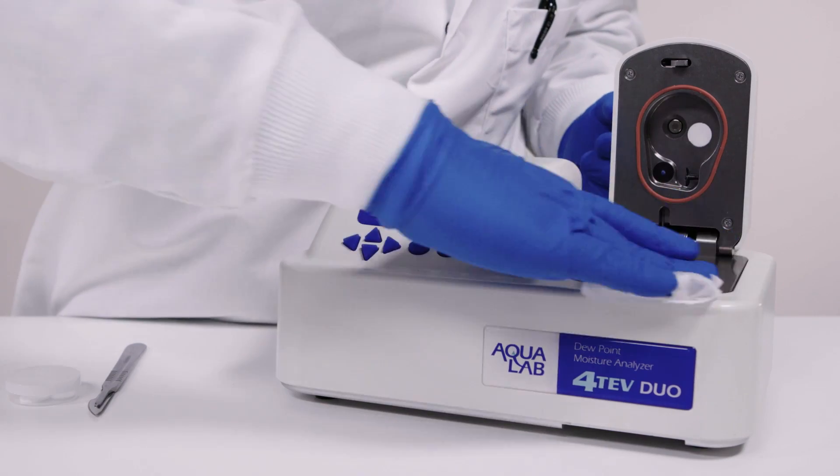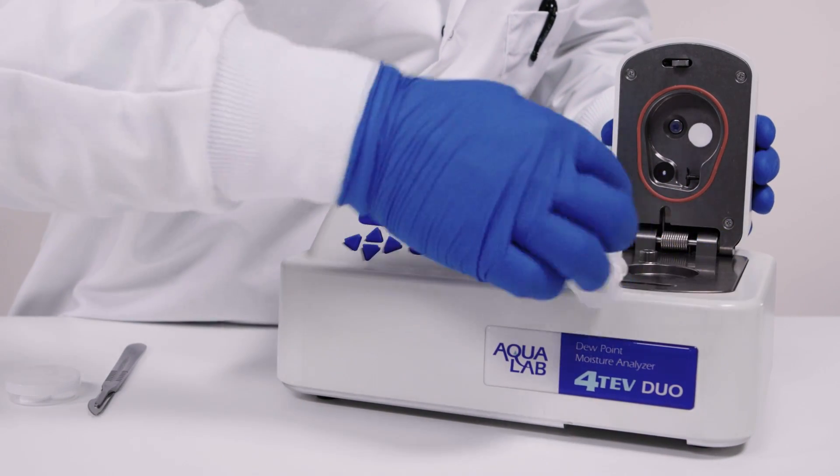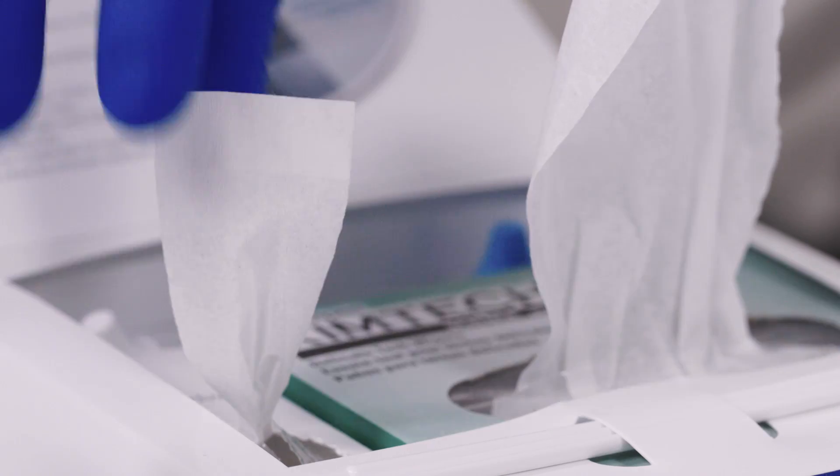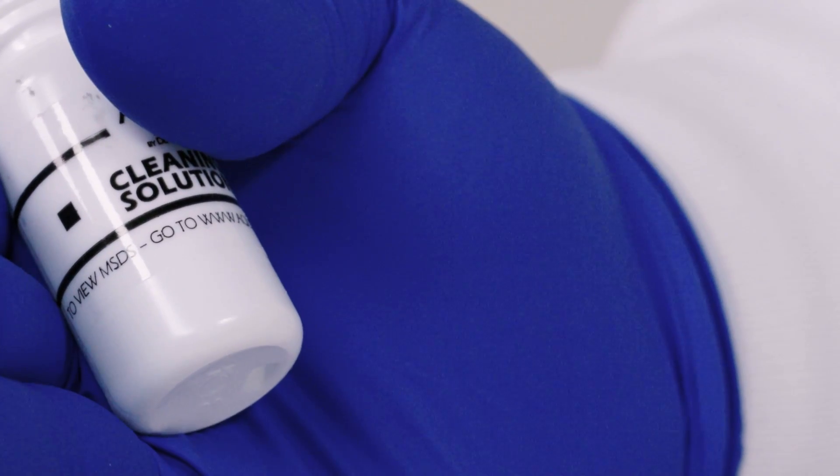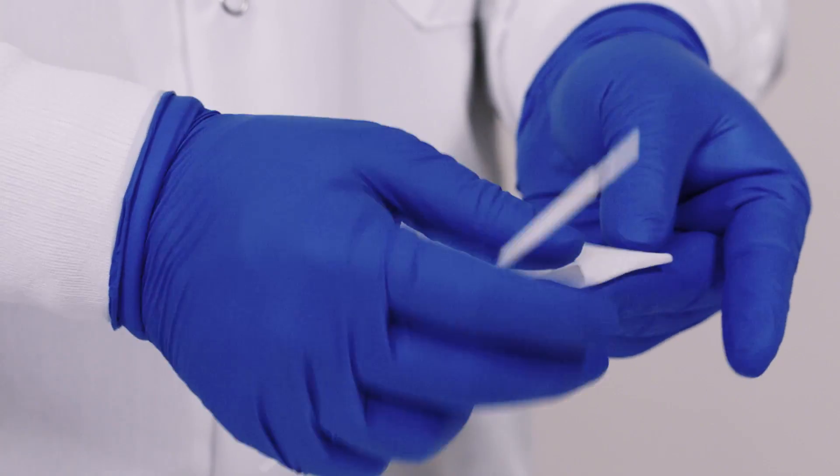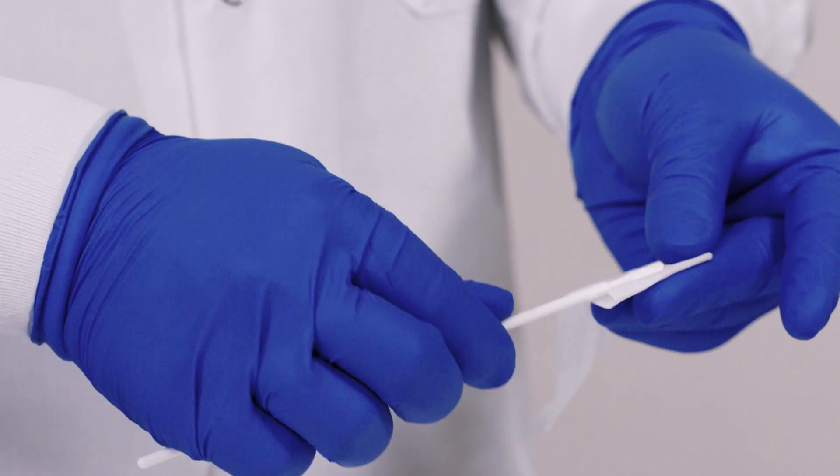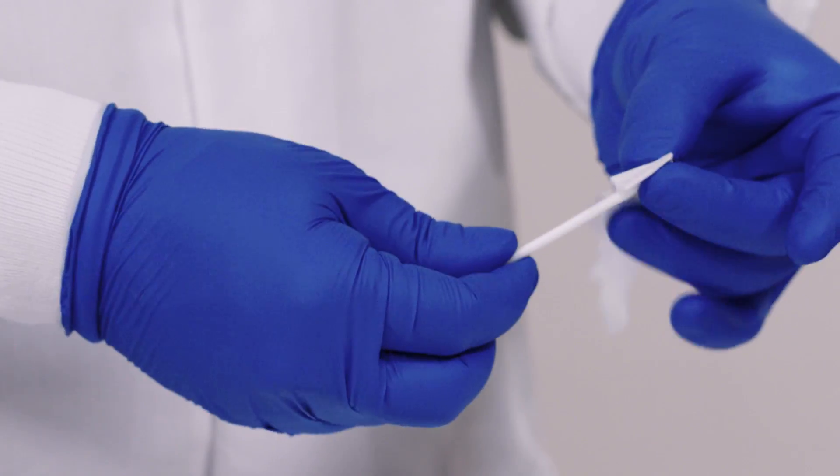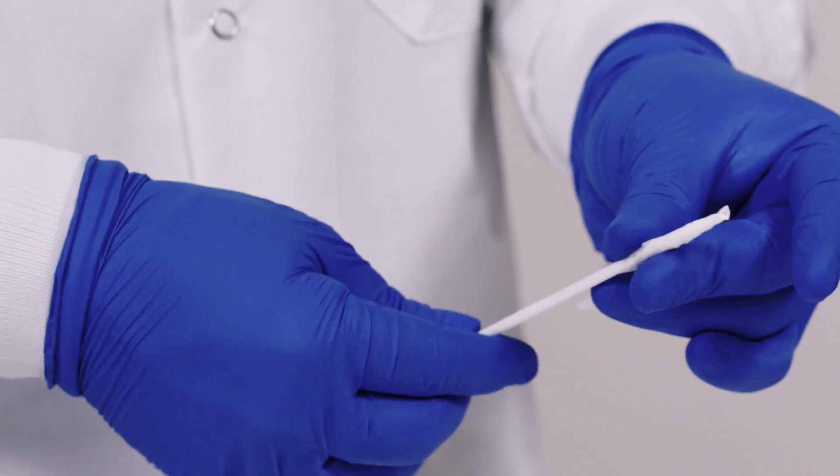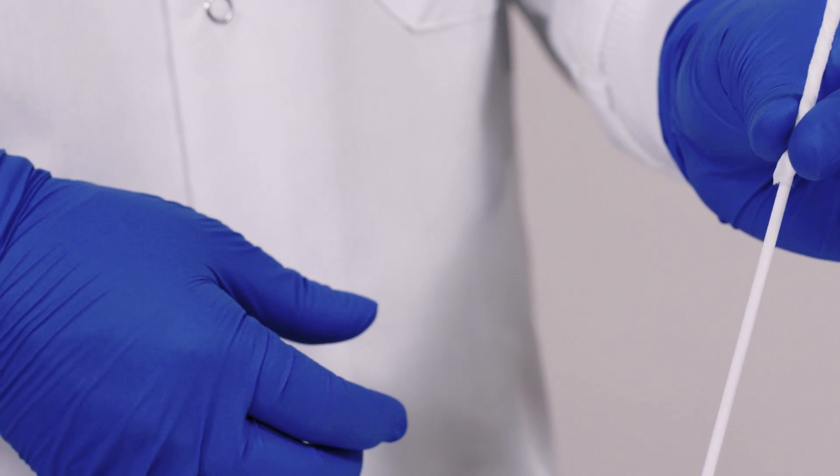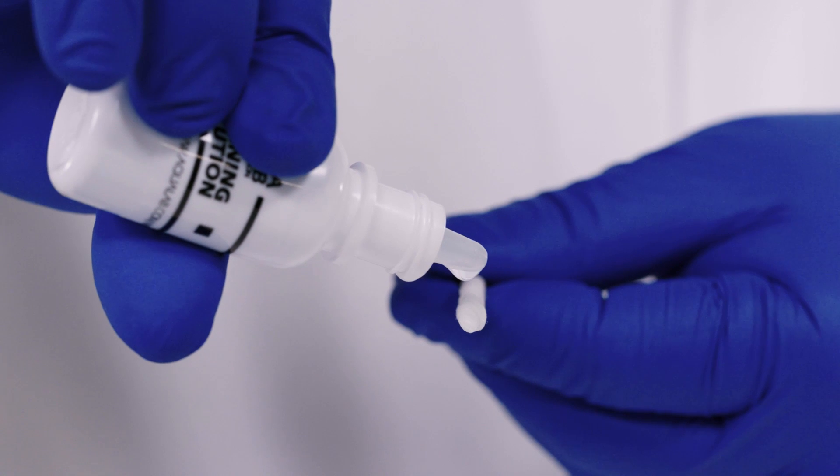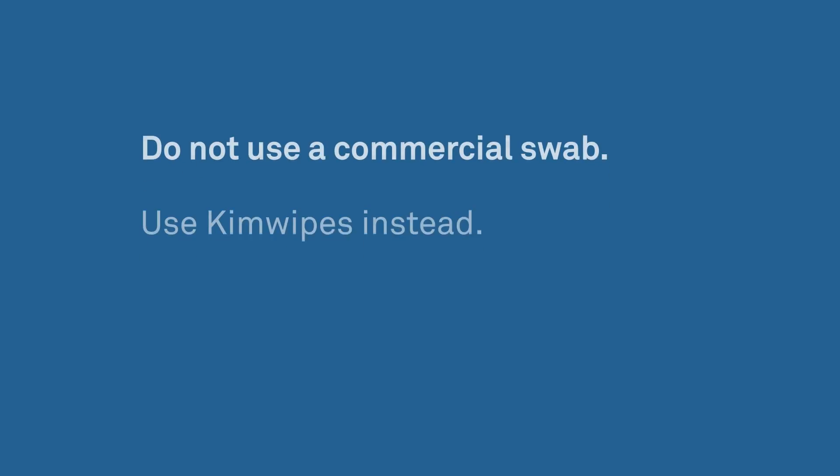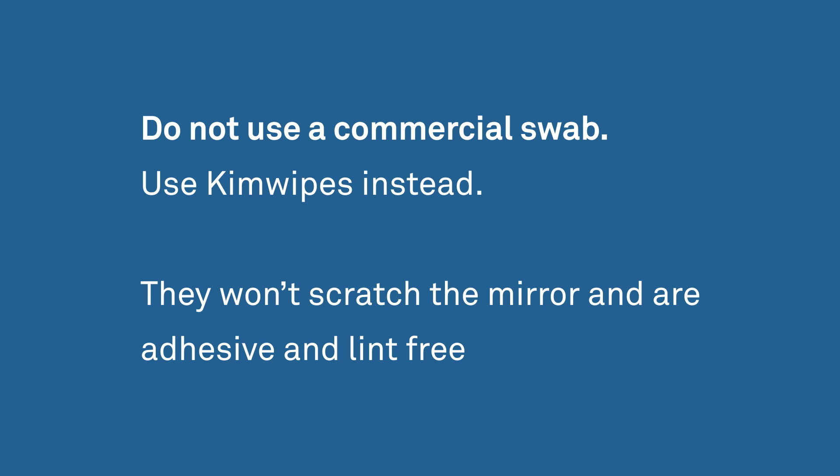Once the surface area of the sample chamber is clean, clean in and around the fan and the sensors. To do this, use a cleaning rod, strips of kimwipes, and isopropyl alcohol or cleaning solution. Wrap a kimwipe strip onto the top of the cleaning stick. The first step to wrapping a kimwipe is to make two folds. One fold over the head of the stick and one over the top to cover the tip. Then twist the stick with one hand while holding onto the kimwipe with your other hand until the head of the stick is covered. It's important not to use a commercial swab because the adhesives used to glue the cotton to the stick will contaminate the mirror and sensors. Kimwipes won't scratch the mirror and are adhesive free and low lint.